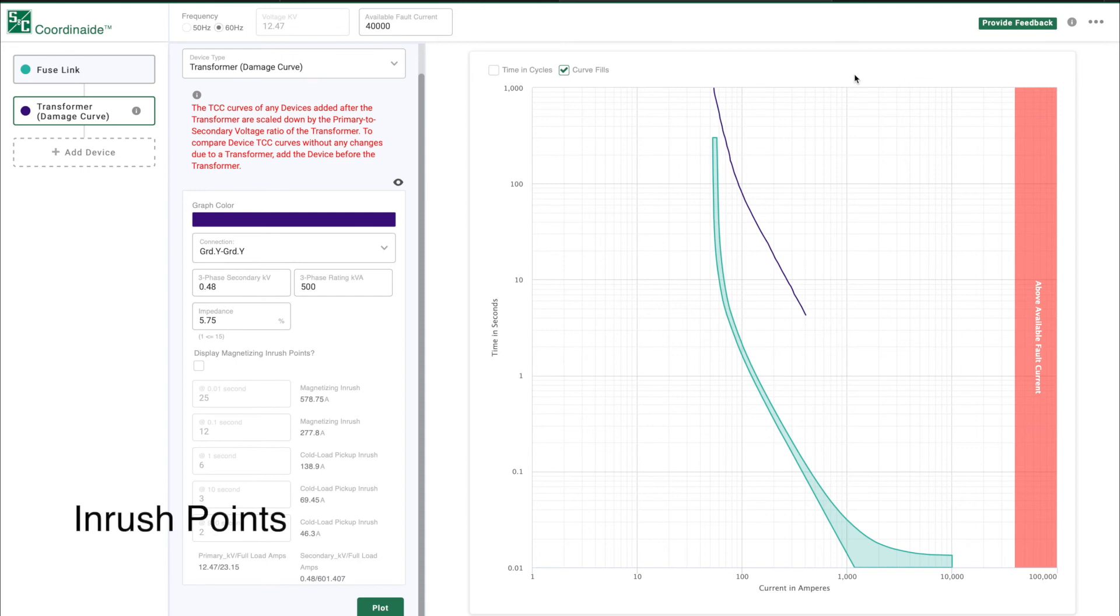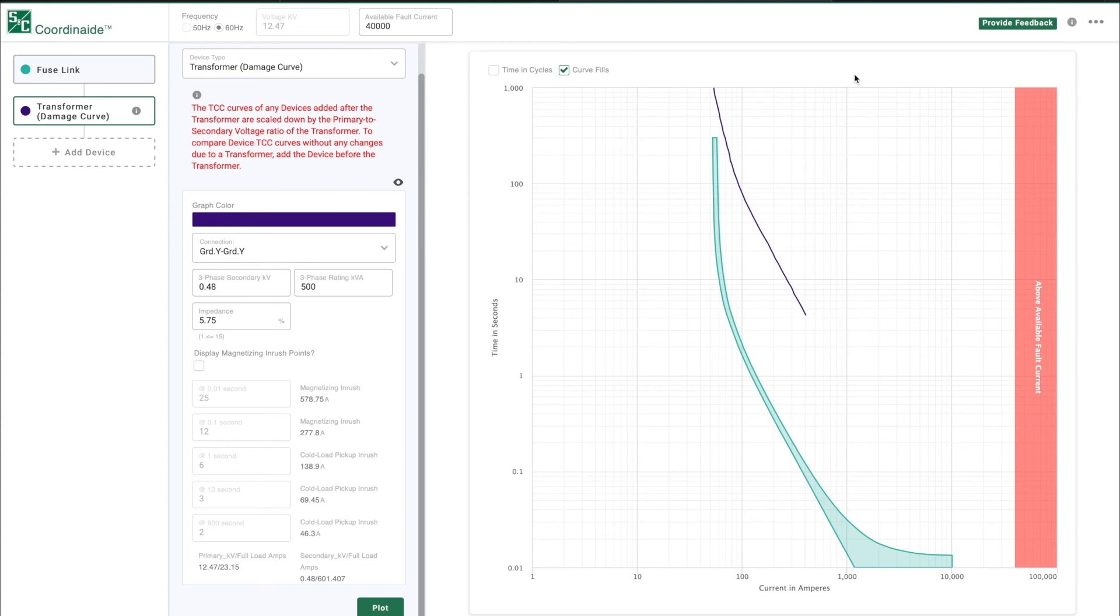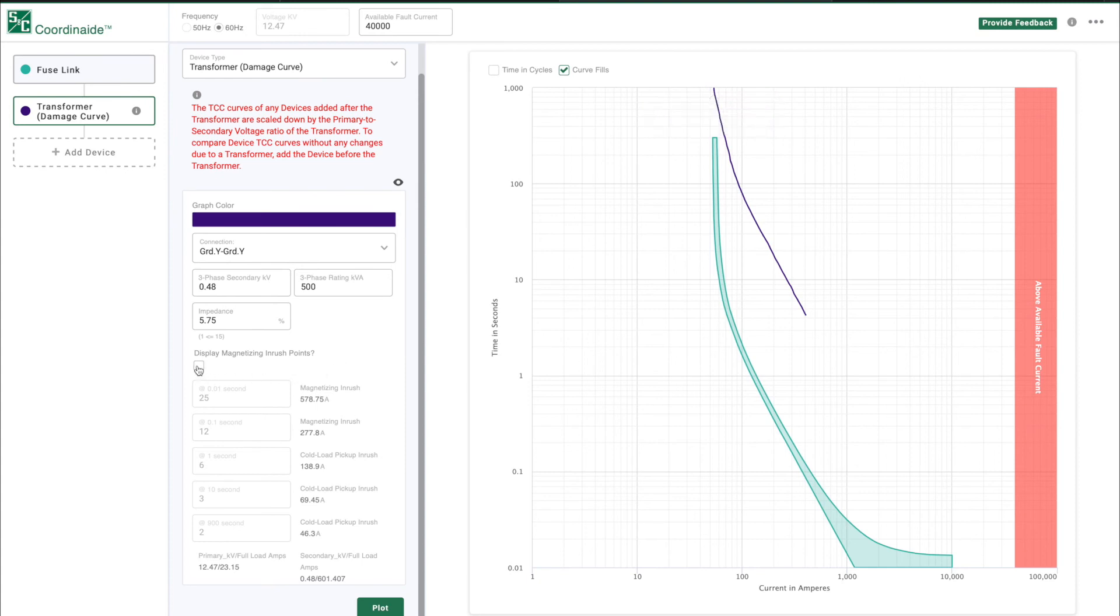When selecting a fuse for transformer protection, we also need to make sure our fuse will not operate for magnetizing inrush and cold load pickup inrush as well. To plot these inrush points on the graph, click on the Display Magnetizing Inrush Points checkbox and then click on the Plot button. You can see the inrush points on the graph.